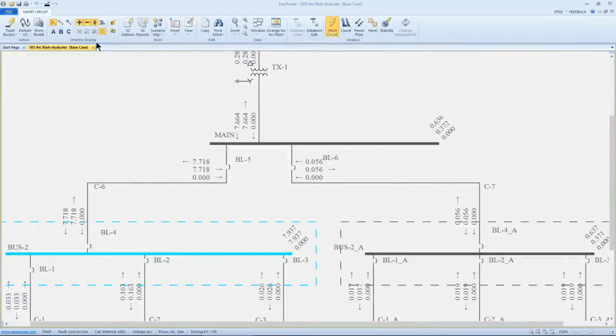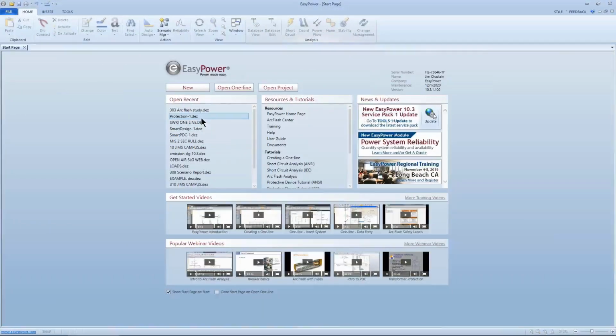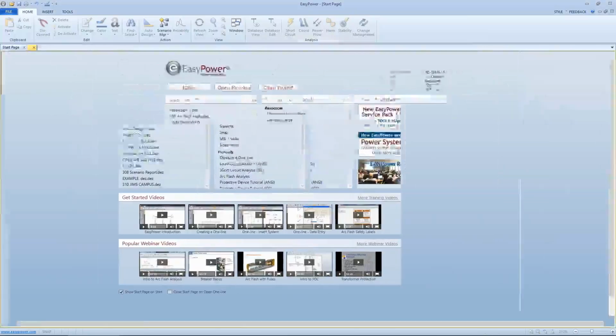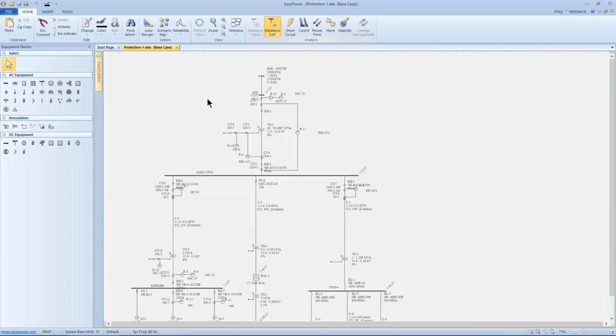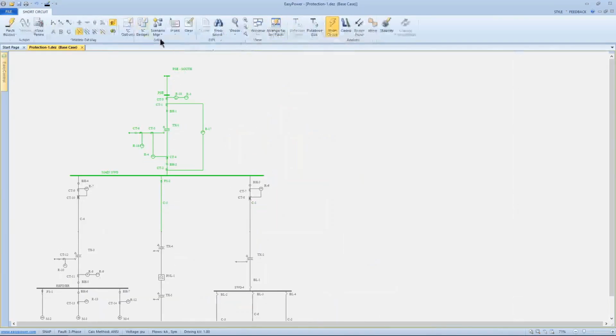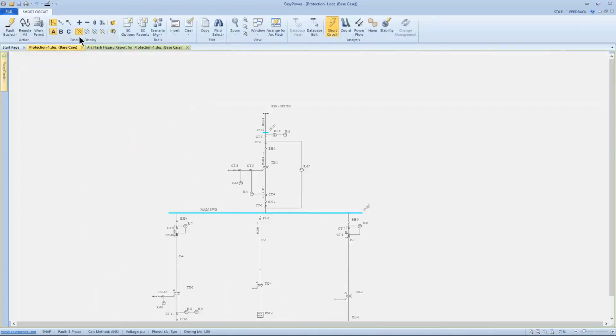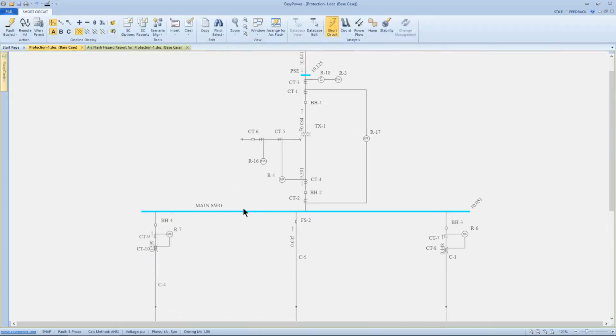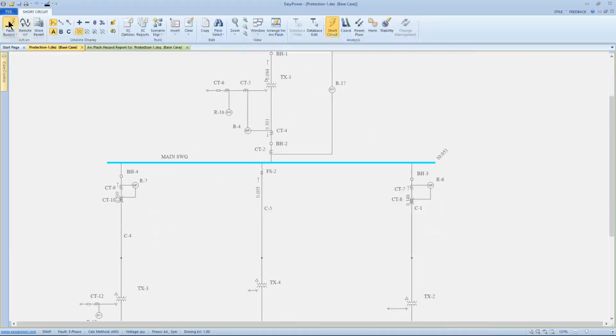application. So I really do want to jump out of here and go to a little bit more complex system. What we're talking about is, in short circuit, the ability to display asymmetric faults. We've already discussed that the three-phase fault is a balanced fault, and to see a difference in the different currents, we would be talking about an asymmetric fault. When we fault all the buses in a three-phase balanced fault, again, I'm looking only at the A phase, let's fault everything.